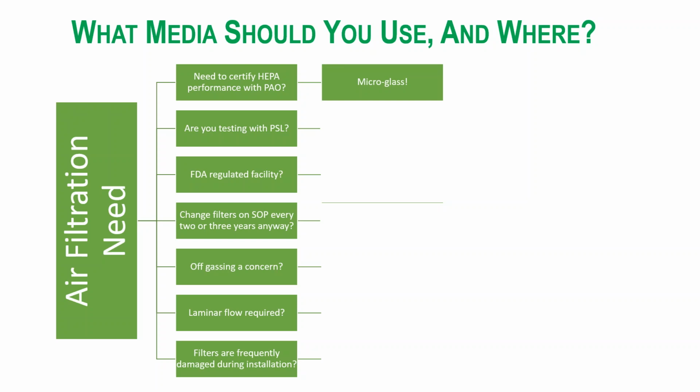Are you testing with PSL, polystyrene latex spheres? If you are, you're kind of unusual in the market. No offense, but it's not something that we usually see in the biospace. It was designed to test PTFE. So if you are using PSL already, then PTFE is a great choice for you. I would say probably 0% of Canadian biolabs are using PSL, so probably not being used in your facility right now. And you do need a whole other certification technology in order to use them.